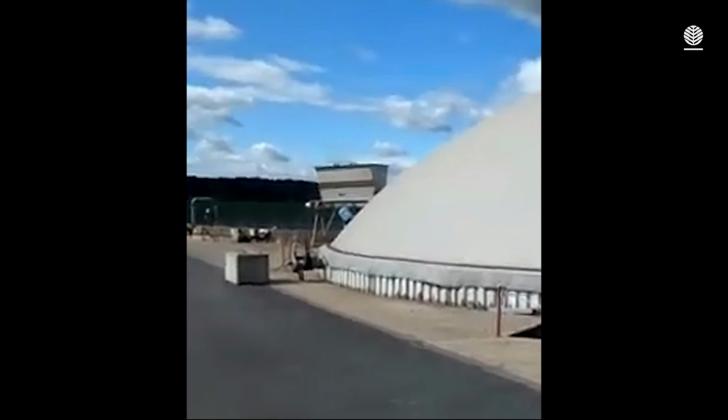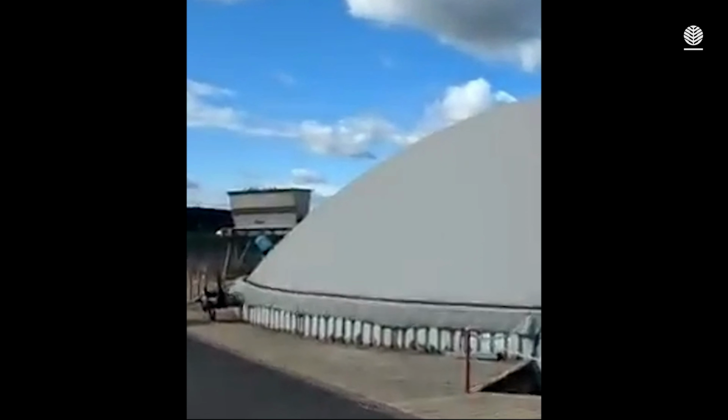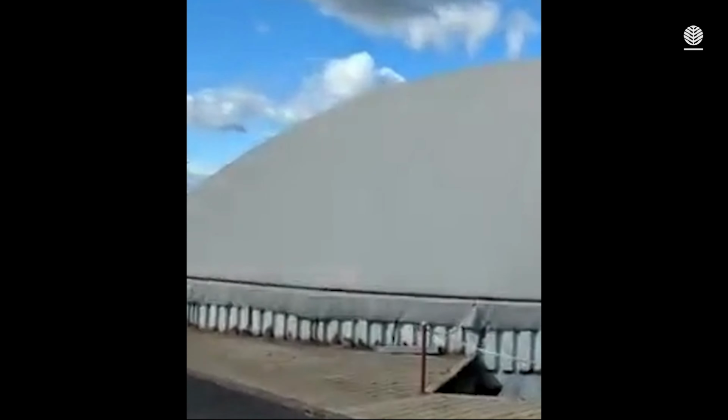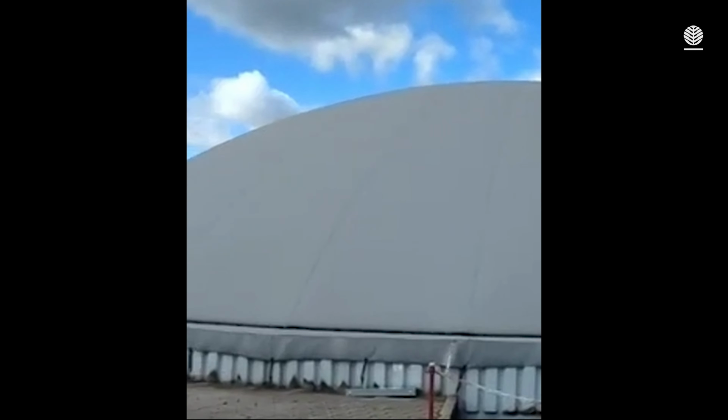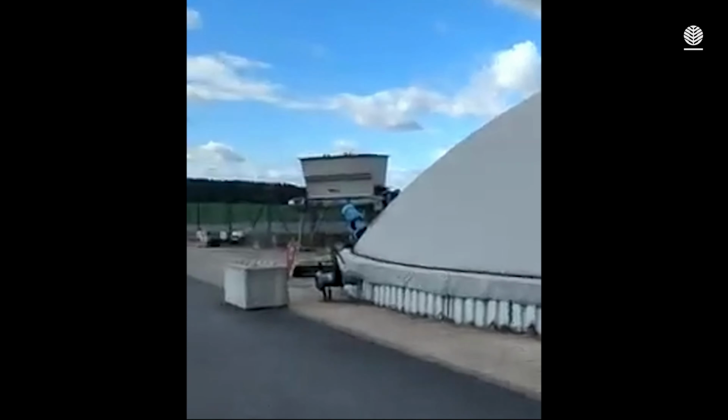In this case, we have a combination of liquid storage and gas holder. I'm not really 100% convinced of this system. I like it more if the gas holder is external and the tank is separate, so it's an extra system. It's safer to operate.